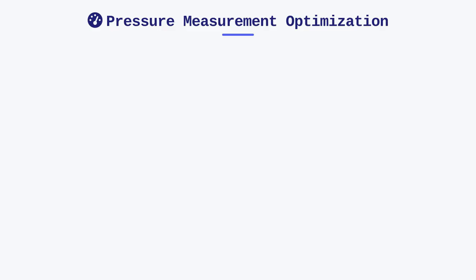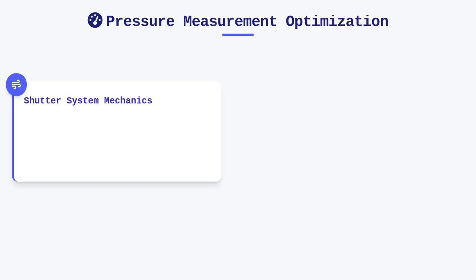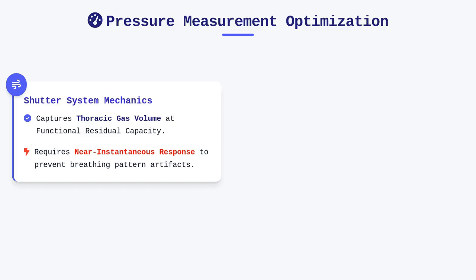To ensure these pressure changes are captured accurately, we must account for the mechanical influence of the shutter system itself. The closing of the airway shutter at the end of a normal expiration allows us to measure the thoracic gas volume at the functional residual capacity level. However, the shutter mechanism must operate with near instantaneous response times to prevent artifacts caused by the patient involuntarily adjusting their breathing pattern during the brief occlusion.